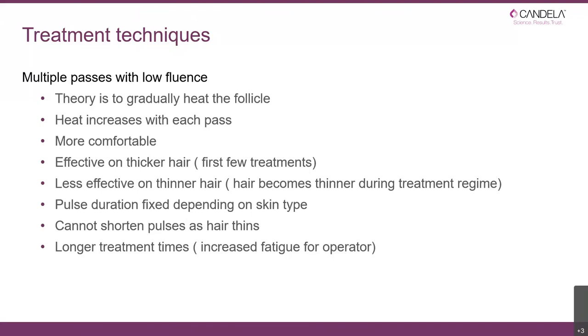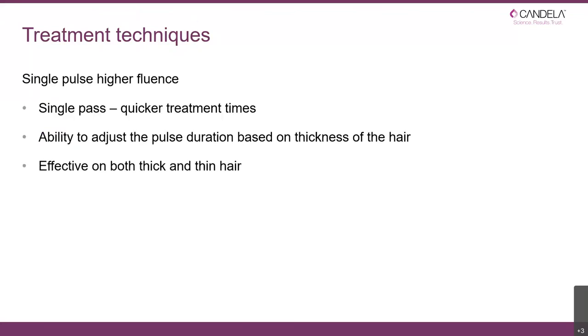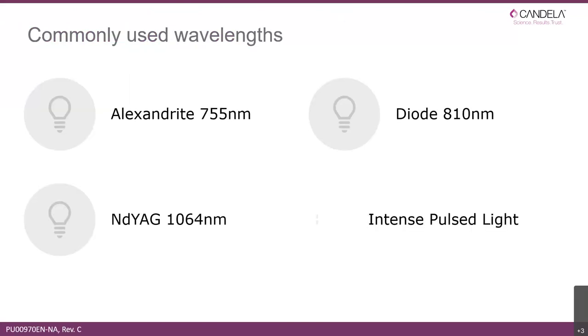With multiple pass diode systems, the pulse duration is generally fixed depending on the skin type, which means you don't have the ability to shorten your pulses as that hair becomes thinner. And because you're doing multiple passes over one area, the treatment time is longer than the single pulse option. The single pulse, higher fluence approach means one pass — you don't double pass or fire two pulses in the same area — so treatment time is quicker. You have the ability to adjust pulse duration based on the thickness of the hair, making it effective on both thick and thin hair, and you can adjust the spot size for speed and area coverage.